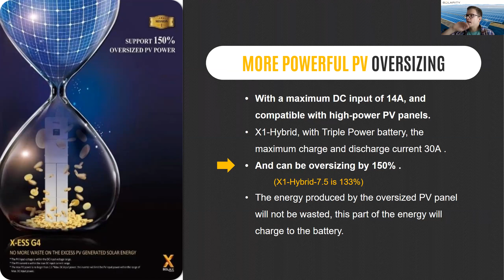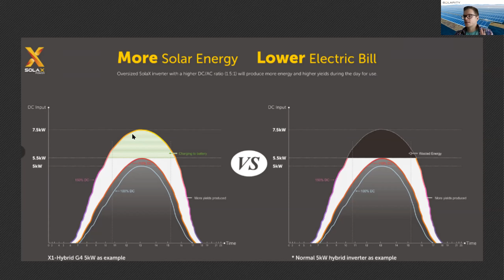But without an energy storage system, oversizing doesn't make much sense, because the extra energy will always be clipped. Like you see on the diagram on the right, the extra energy from oversizing the system will be clipped, so the energy will be wasted. But with an energy storage system, the extra energy from oversizing can always be stored inside the battery system. So in this case, oversizing really makes sense.